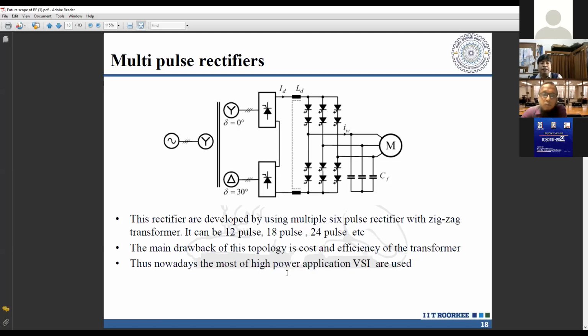So we seek a multi-pulse converter, called a 12-pulse converter, physically available here. This uses the power system vector group—star-delta conversion doesn't need a special transformer. But for other pulse converters, the phase shift differs; for a 24-pulse converter with a 15-degree phase shift, a special purpose transformer is required. This way we can reduce the harmonic component on the supply side. For megawatt-level power handling machines, this is a suitable solution—going for 18-pulse, 12-pulse, etc., considerably reduces the power quality problem.